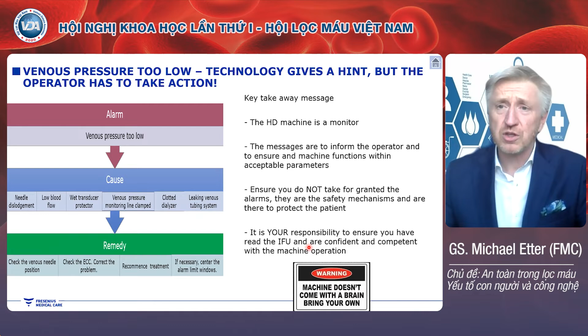So the first thing when you have this alarm is not to reset your alarm, but to look at your patient, to make sure that all these things are in order and that there is no problem, and then you can adjust as needed. And as you can see, there are various ways to correct low venous pressures, as you see here in the green box, and that's what you then do. So the key takeaway message here is the HD machine is a monitor at the moment. The information that is displayed there is for you to take the appropriate action.